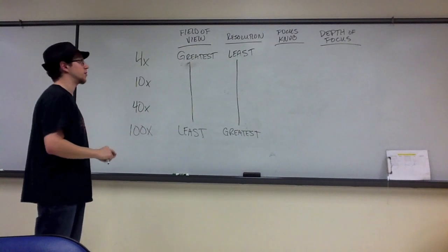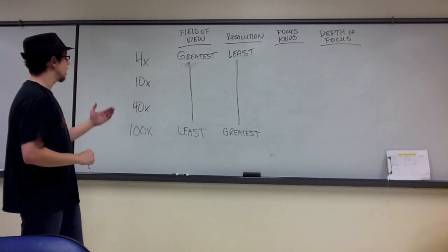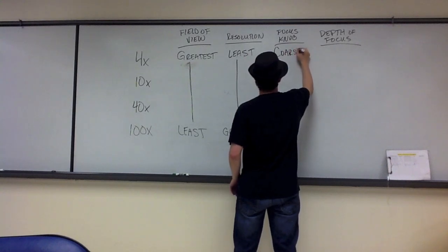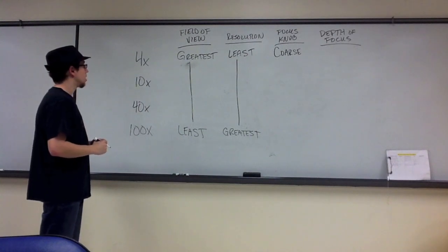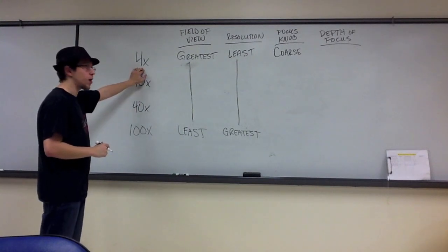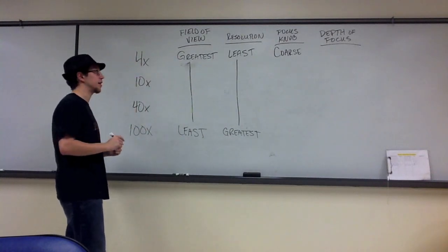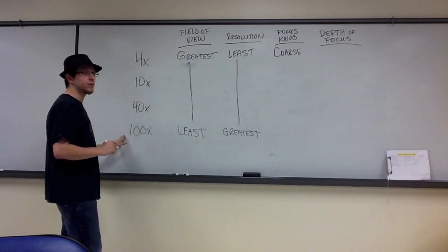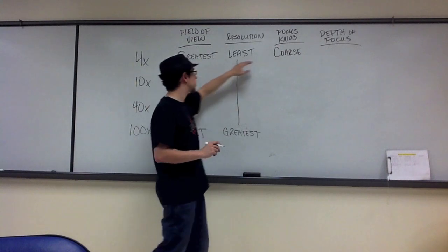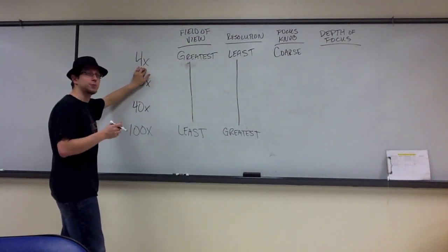Which brings us to the focus knob that we're going to use with each. 4x should always be used in conjunction with the coarse focus knob. Whenever you place a sample on the microscope, you should always start by placing your objective lens at 4x and using the coarse focus adjustment knob to bring your sample into focus. Always start with 4x and coarse. I can't stress that enough.